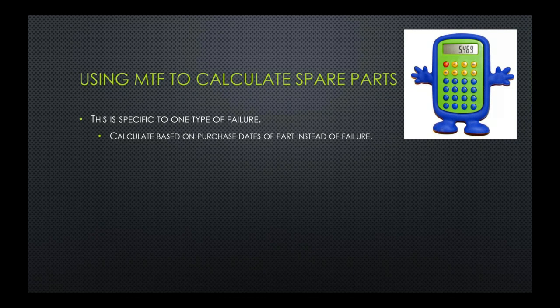And this gets a little harder to do, because when you go to buy parts, even if you buy them from the manufacturer, sometimes those part numbers change. You have to know if those part numbers have changed to make sure you can actually see it, or you have to use your database in a manner that allows you to see how many times a power supply was changed or a tube was changed on that piece of equipment. An X-ray tube is easy, but if you talk about power supplies or switches or other items you might have multiples of in a bigger, complex unit, you might have four or five different power supplies in the unit, and you need to know if it was that power supply.